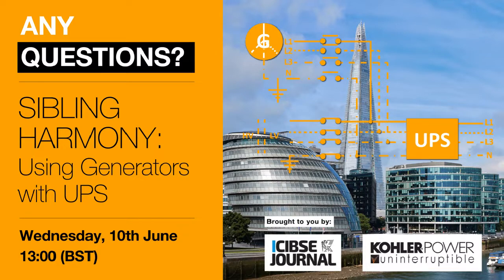And now a question from Vicky. How long will a generator run for? Okay. Fuel tank. Yeah. How long's a piece of string? We can set that to run for whatever time we want. Some generators are primary power and run continuously, 24/7. Pete, if you want to carry on. It's all about how big the fuel tank is. The generators these days are designed to run 24 hours a day, 7 days a week. Whatever the kVA is, it should be able to run. It's all about fuel supply.